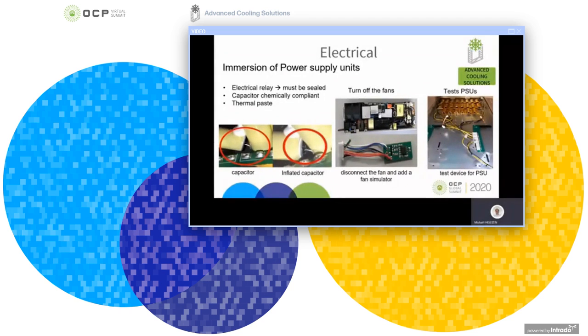Regarding power supply units, several points must be monitored in order to validate their compatibility and their ability to work within dielectric liquids. The electrical relay must be sealed. The capacitor must be chemically compliant. In the picture on the left, you can see a capacitor which inflated after immersion. This can sometimes go as far as tearing off the component. And the possible presence of a thermal paste in the power supply unit must be checked. Therefore, you have to check that the fan is perfectly disconnected and there is no fault signal. For this, you can, for example, use a fan simulator as you see in the central picture.